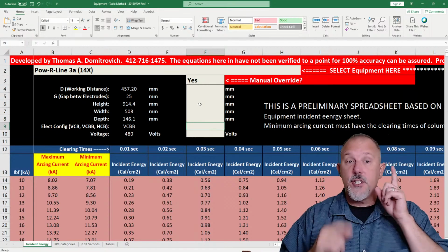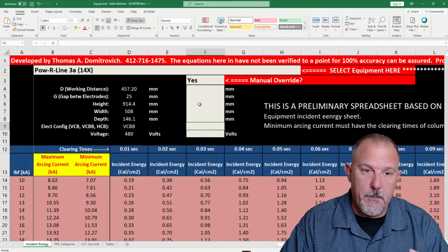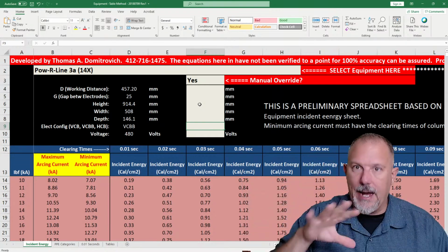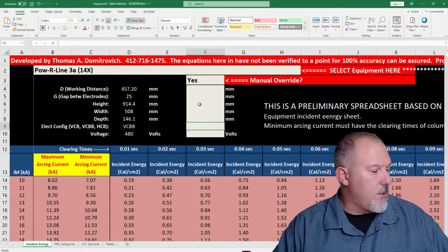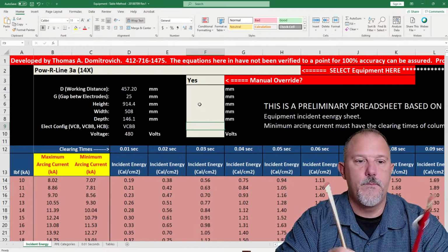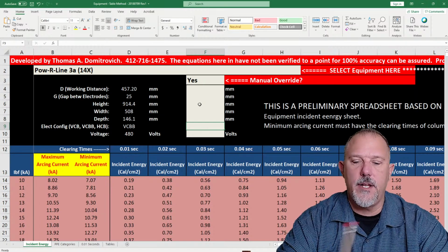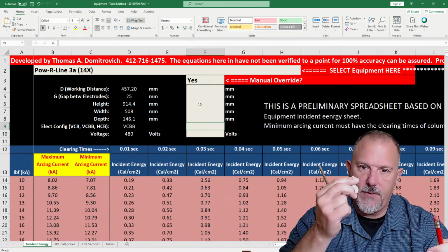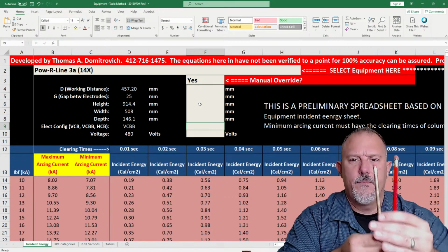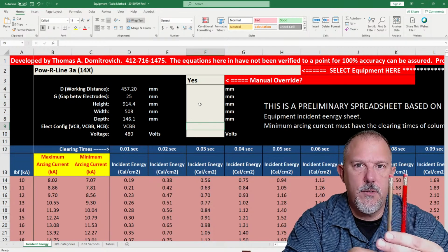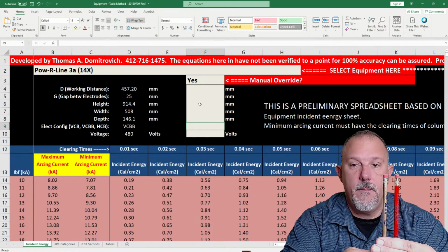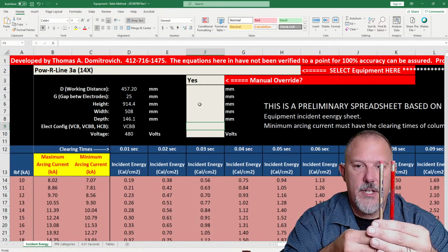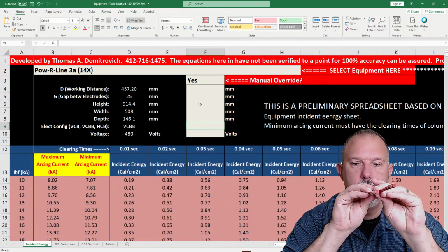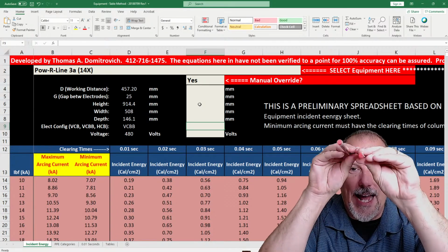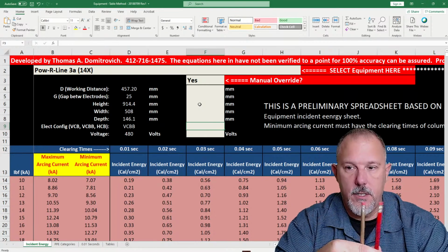How about the electrode configuration? What is VCB, VCBB, HCB, and then there's ACB, etc. For outdoors? Let's go back to my pencils. If you look at a panel board, I'm going to take that and use it as an electrode. So I have my bus, and this is my panel board. A panel board bus goes up and down like this. That is VCB. HCB is when my bus is this way, with the bus looking straight at me. And what do we know about an arc?